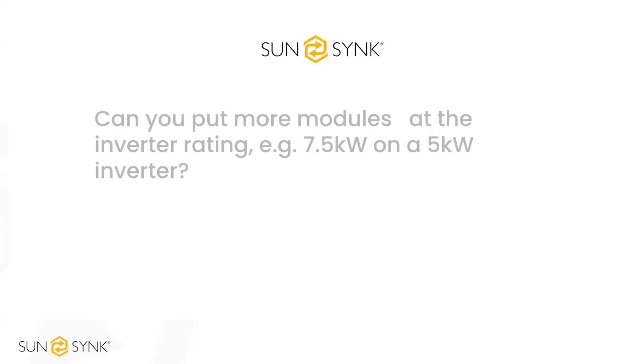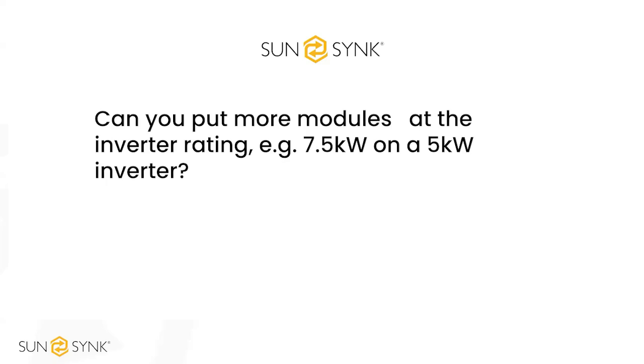Can you put more modules than the inverter rating, e.g. 7.5 kilowatt on a 5 kilowatt inverter? We give the oversizing sizes. For example, on the 5 kilowatt, we say you can connect up to 6.5 kilowatt of PV. You can connect more than that. The most important thing is to make sure that your string voltages are within the parameters. On our data sheets, you will see we've got the MPPT range. Try and stick to that, because you'll also have an upper limit on the data sheet of the DC string voltage. So let's say the upper limit is 500 volts.